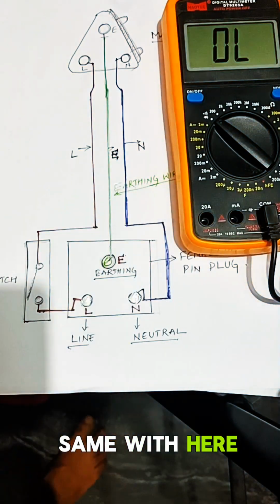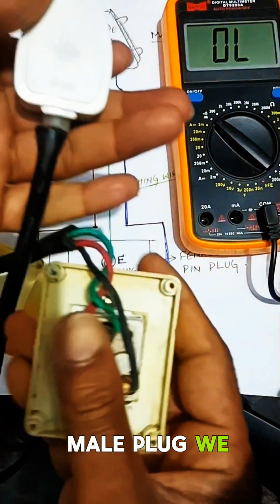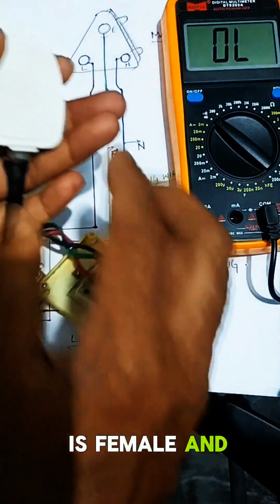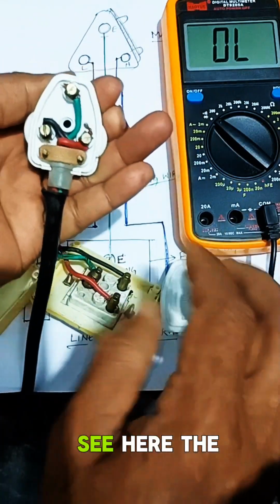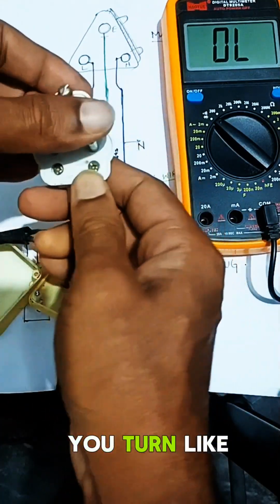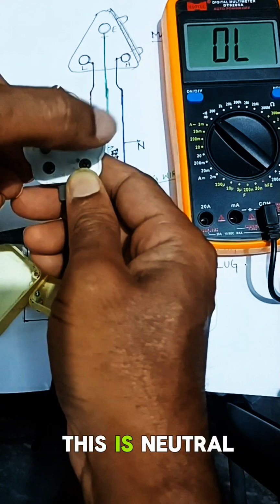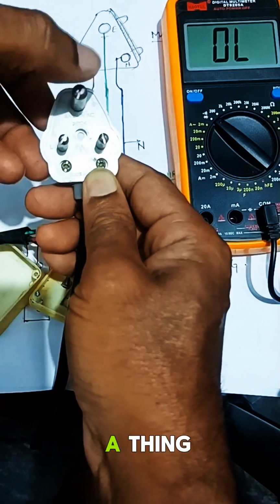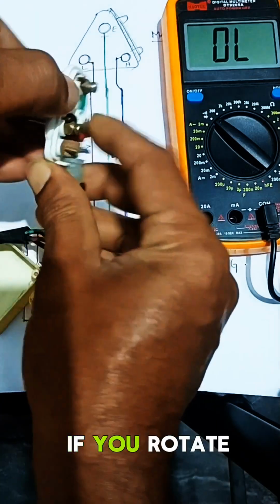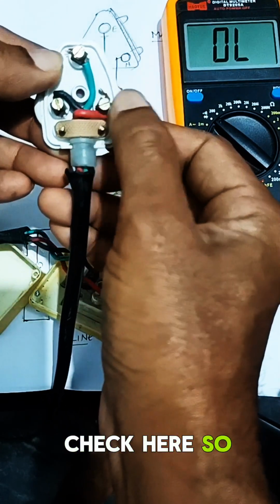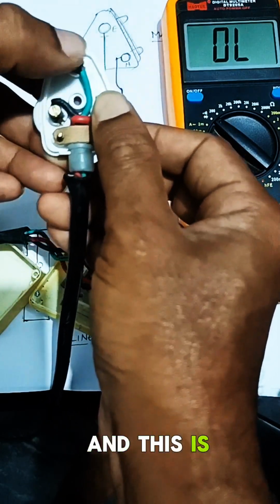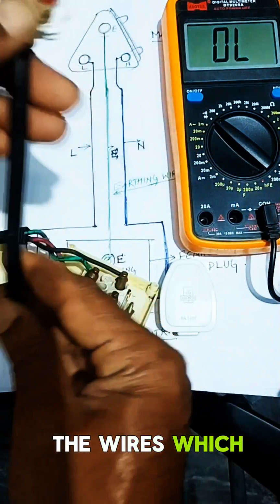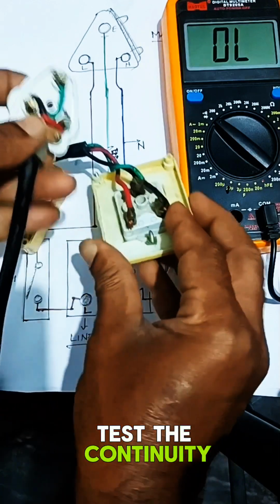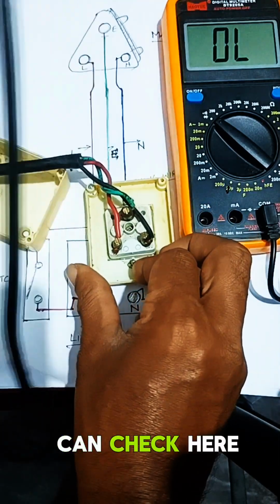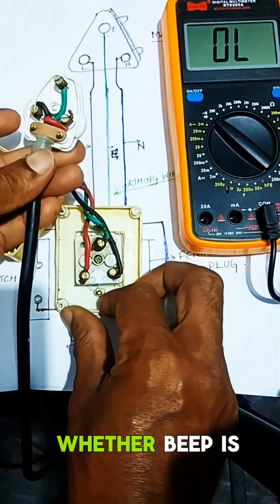Same with the male plug, we have this is female and this is male. We can open it and see the connection. If you turn it like this, this is the line wire, this is neutral, and this is earthing. If you rotate it, it will be vice versa. See, check here: this is the line wire, this is neutral, and this is earthing. These are the wires which are coming. If you test the continuity of those wires, this is a big wire, you can check here. Now we will check the continuity whether the beep is coming or not.